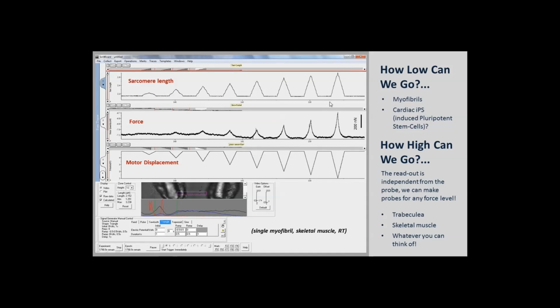How sensitive is the force transducer? How low can we go? This shows you an example where we look at a skeletal myofibril, as you can see many times smaller than a myocyte. And we're looking just at the passive properties here. So we stretch the cell to different lengths. This is the sarcomere response. And here's the force response. You see the error bar. This is only 200 nanonewton. We can easily pick up these forces. Just to keep in mind, if you look at the active force of a myofibril, it will pretty much come to the top of the screen, if not further.